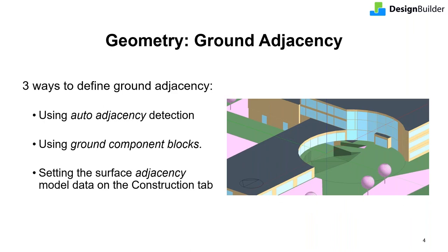Moving on, let's discuss the ways to define ground adjacency in your models. There are three ways to do that. First is by using auto adjacency detection. In Design Builder, the adjacency of a surface is determined automatically based on its position — this is switched on by default. This means that external surfaces on or below the ground plane, that is z equals zero or less, are considered to be adjacent to ground automatically. This is typically applied to surfaces such as slabs on ground or below-grade basement walls.